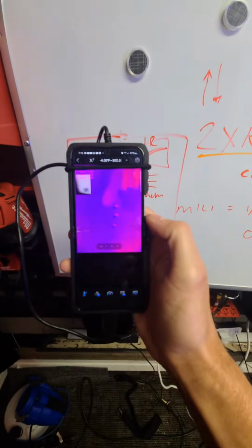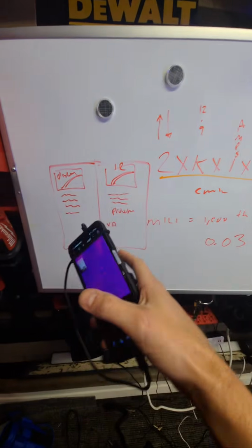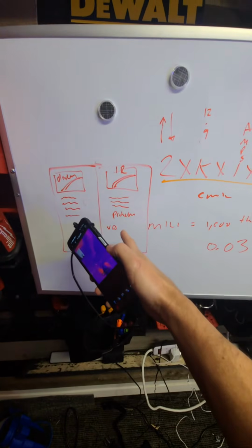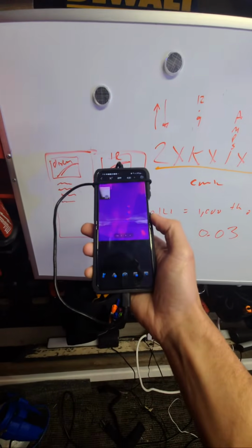Okay, so then you got your infrared and your scanning, right? And we find our loose connection, but we're far from done. We still need to verify it's a loose connection by using our multimeter. We're going to show you how to do that right now, because that itself is kind of a secret. So this is what we do.